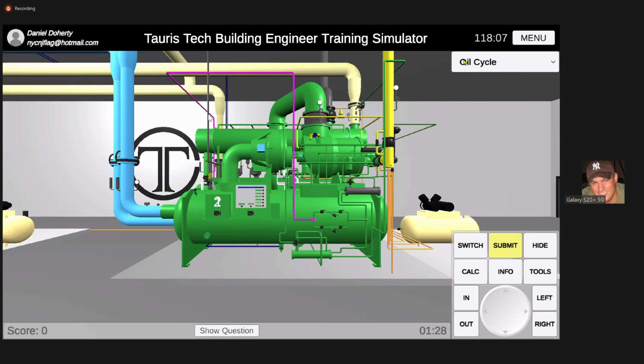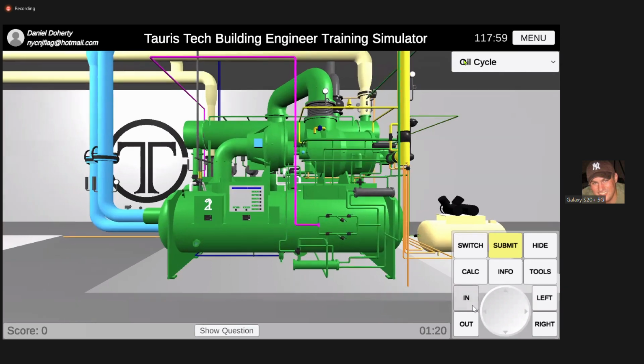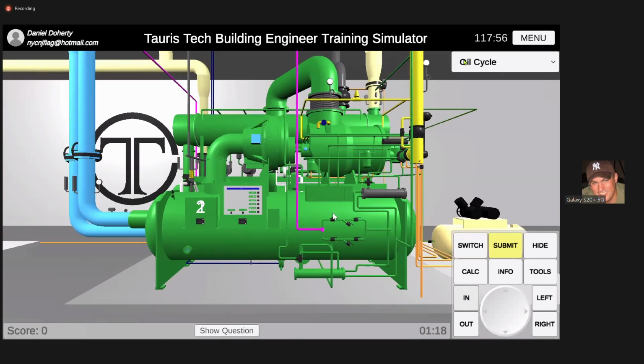There you go. Okay, so you guys see it? It came from over the chiller, across. This is the same exact setup as Metrotech. It's no different. We got this down 100%. So that line comes down, and it comes into your manifold. Here's your manifold. It goes through the manifold. And now it's supplying cooling water to this heat exchanger and this heat exchanger.